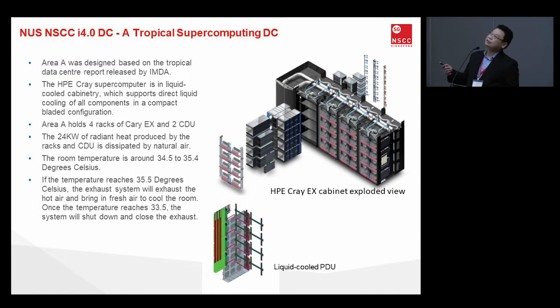All right, so as mentioned, the HP Cray Supercomputer is a liquid cool system, which supports direct liquid cooling to the chip, and in the bladed system. All right, so the area A hosts 4 Cray EX and 2 CDUs. As Paul mentioned, this is a unique thing. We actually have two CDUs for this particular system because Singapore is hot, that's one. The temperature that is running through the system is much higher than most systems that we see. So hence, the second CDU is added in as additional capacity and as a precaution also to prevent the system from overheating. All right.